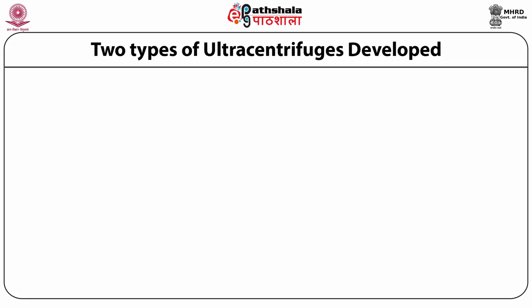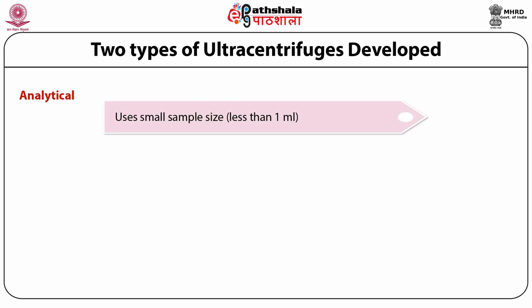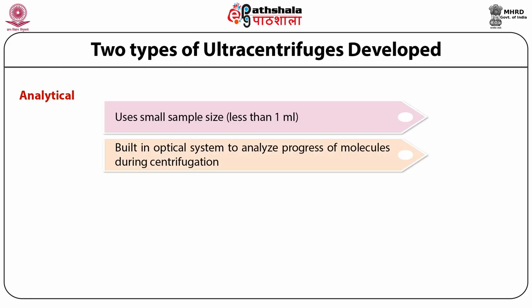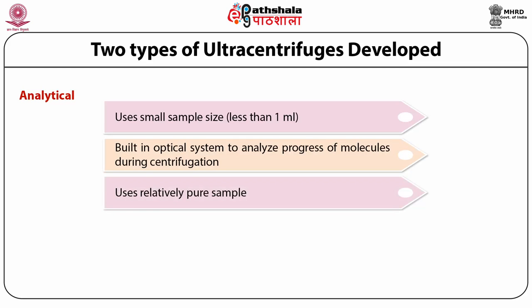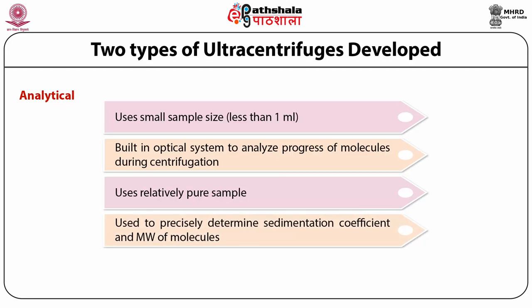Ultracentrifuges are divided into two categories depending upon the application: the analytical ultracentrifuge and the preparative ultracentrifuge. The analytical ultracentrifuge uses a small volume — less than 1 ml — and has an inbuilt optical system to analyze the progress of molecules during centrifugation. In analytical ultracentrifugation, relatively pure samples are used for measurement of biophysical properties and characterization, and it precisely determines the sedimentation coefficient and molecular weight of the molecule.